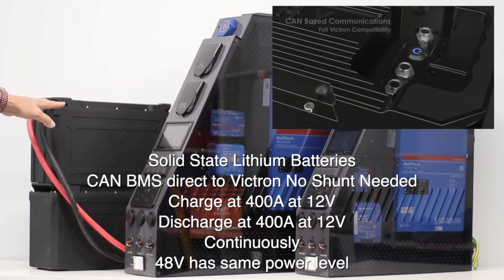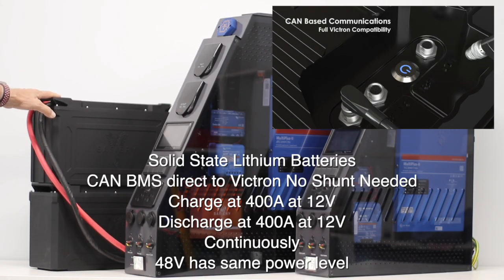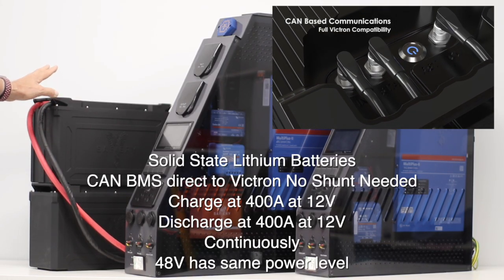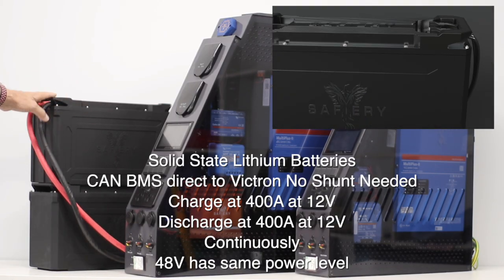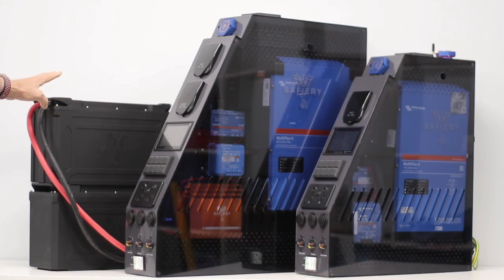These are CAN-based so we don't need a shunt — it reads the battery directly. They have a 1C charge and discharge rate, so that's 400 amps you can run out of here on 12 volt, and the same equivalent current on the 48 volt, and you can charge at a high rate.